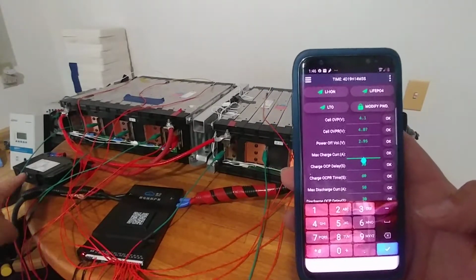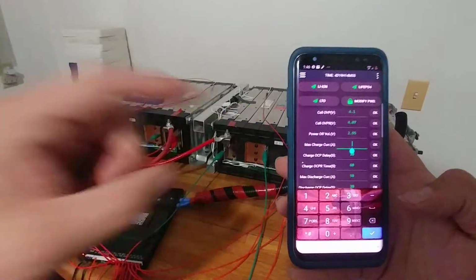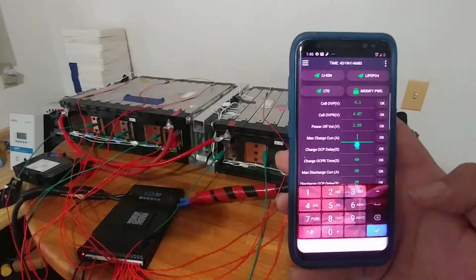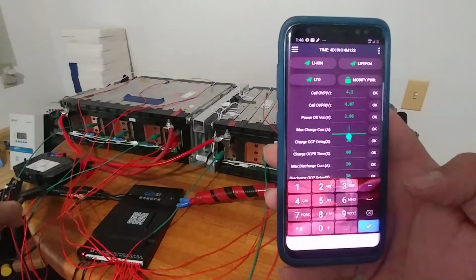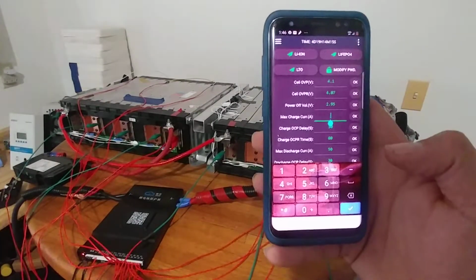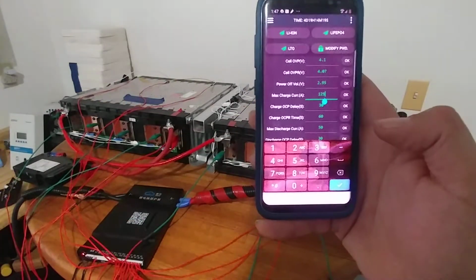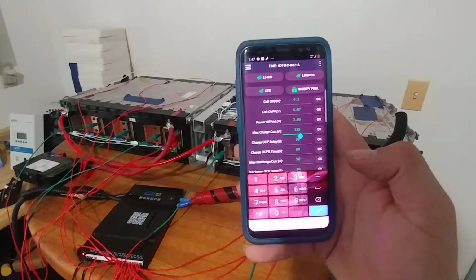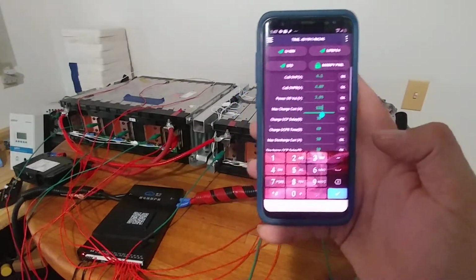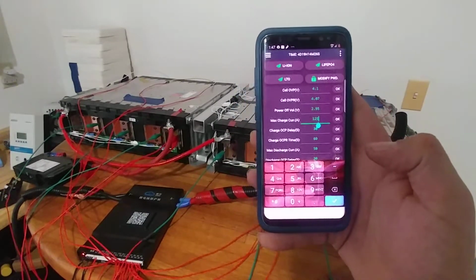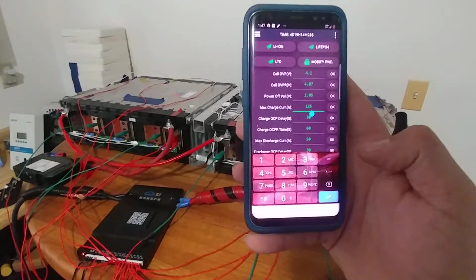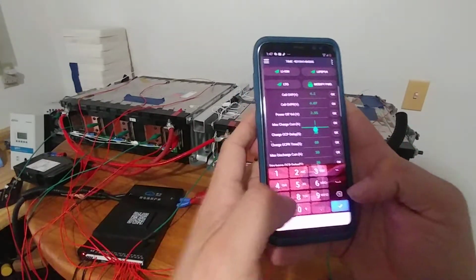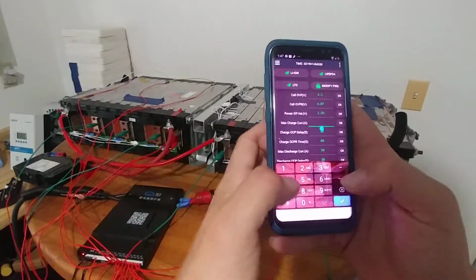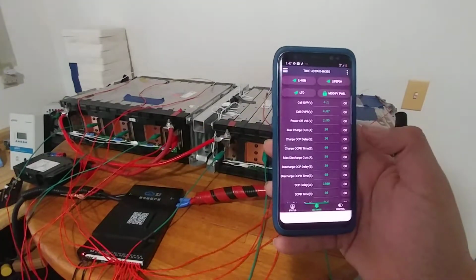I don't really want this to ever trip. I want this to trip because this is a MOSFET trip, and it's going to automatically reset itself based on these other values, whereas this is going to require manual intervention. So I definitely want to have this value set lower than the value of the manual breaker. The value of the manual breaker is simply a secondary failover in the event that this does not work. But for testing purposes, with the thickness of this wire, we're actually just going to set this to 50 amps.